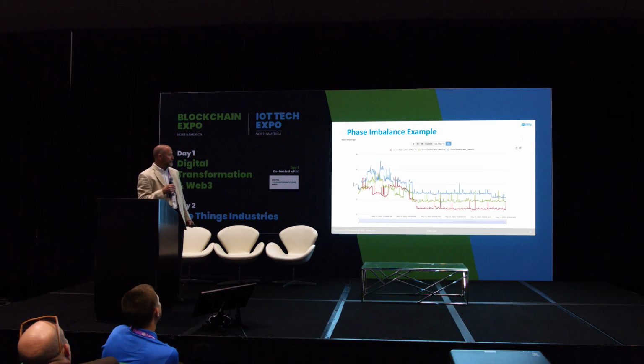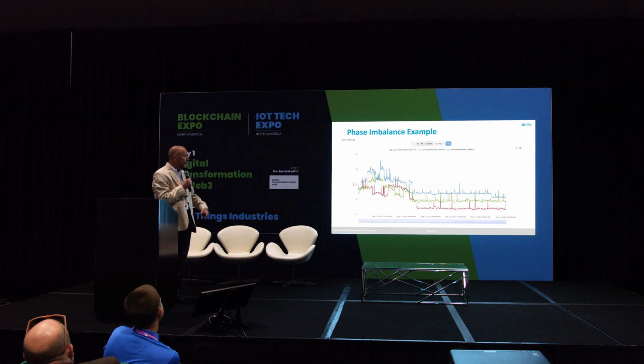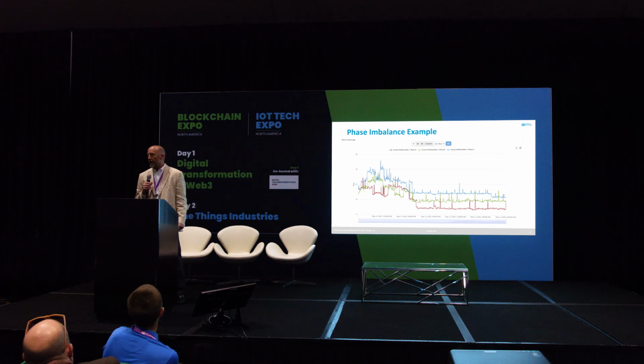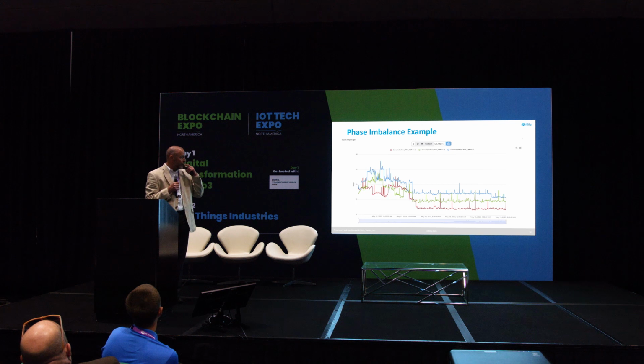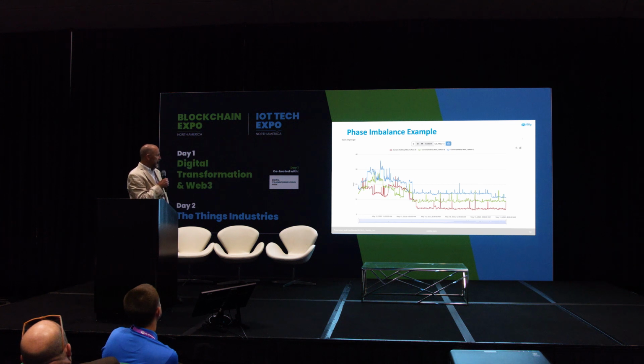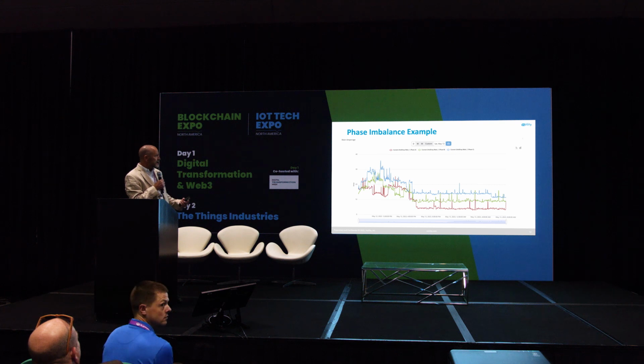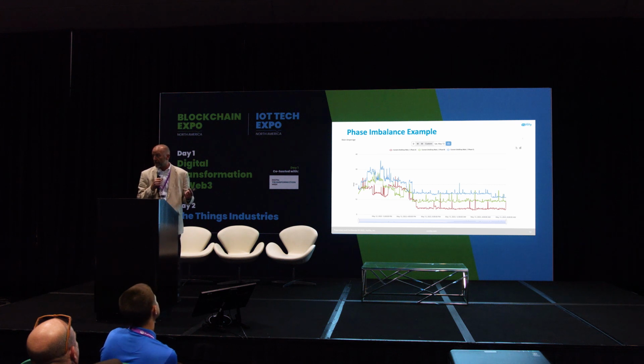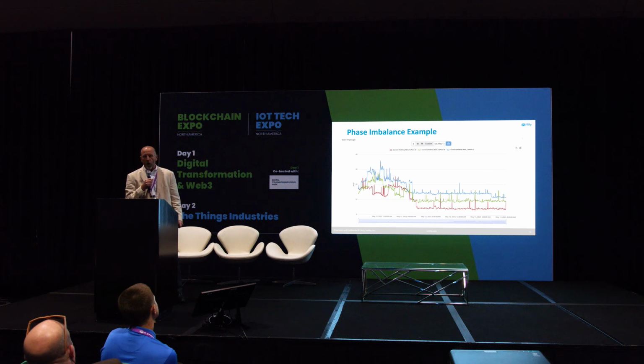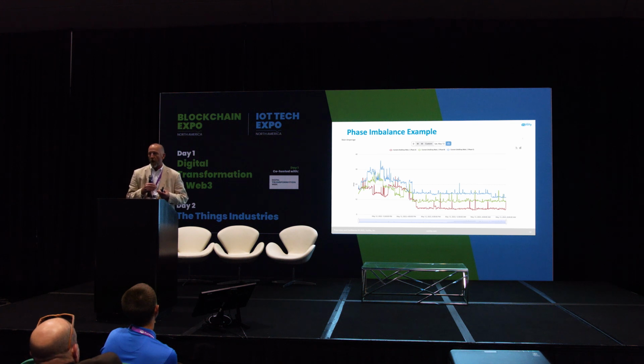This is an example of what I'm talking about, actually from our building in Sandy, Utah, where we have hot drops installed. You can see on the right-hand side that phase C is more than phase B, and it's quite a bit unbalanced. Now, these loads aren't that great, so the benefits of balancing them may not be worthwhile.